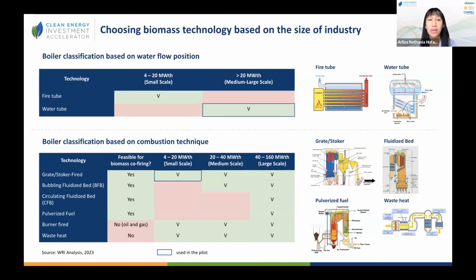For boiler classification based on combustion technique, there are five types. The first is the grate or stoker fired, which can be applied across all scales of industries. Then there is the fluidized bed, which has two types, bubbling and circulating. The third type is the pulverized fuel, which can only be applied to large scale industries. And then there are two other types, the burner fired and the waste heat.